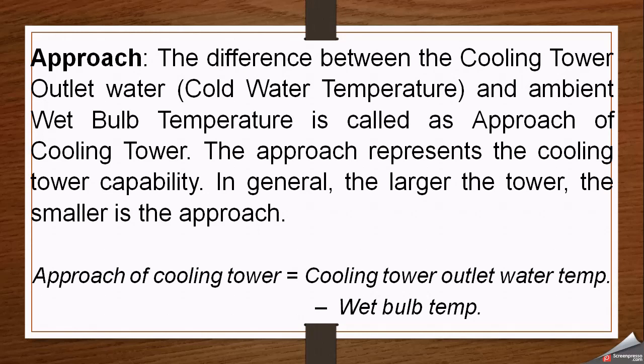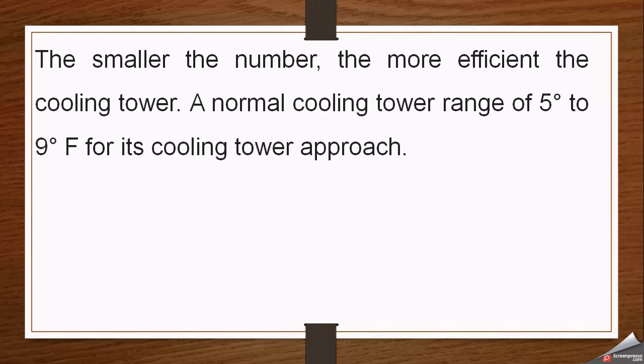The approach represents the cooling tower's capability — how much the tower can reduce the temperature of the hot water coming from the system to produce cold water. In general, the larger the tower, the smaller the approach. Approach is calculated as: cooling tower outlet water temperature minus wet bulb temperature. The smaller the approach number, the more efficient the cooling tower. A normal cooling tower range of 5 to 9 degrees Fahrenheit is used for good operation; if it goes beyond 9, efficiency decreases.